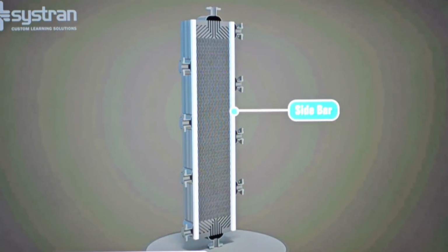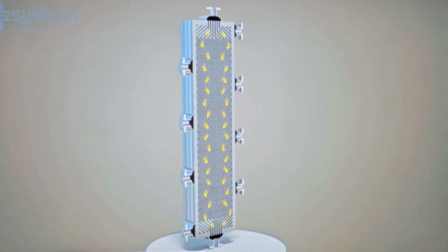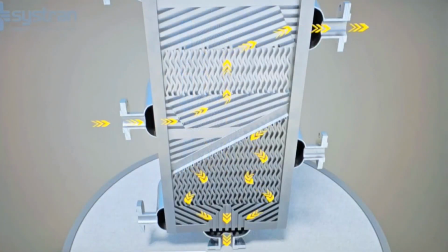Sidebars prevent the fluid from mixing between the sheets. The corrugated fins direct the feed gas flow into a vertical pattern, while the fins for the refrigerants flow in a horizontal pattern that achieves a cross-flow between the warmer feed and the cold refrigerants in each modular section.